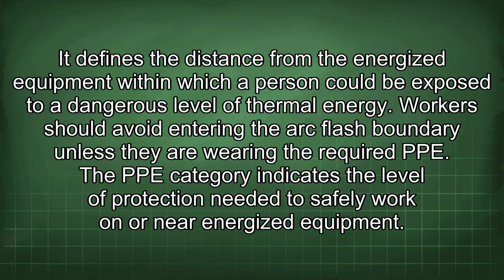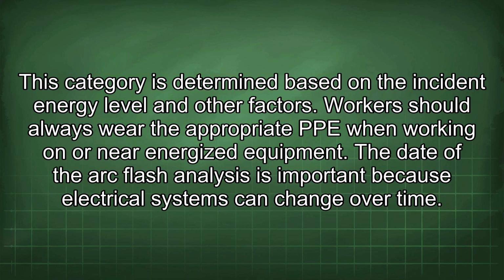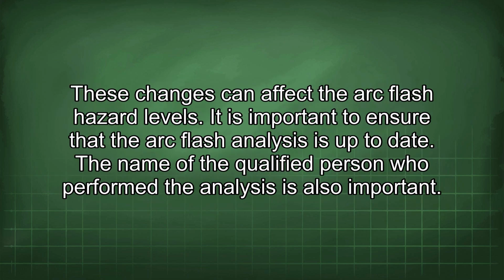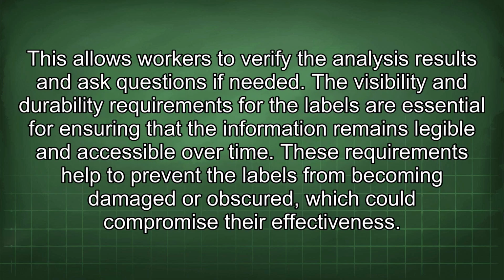The PPE category indicates the level of protection needed to safely work on or near energized equipment. This category is determined based on the incident energy level and other factors. Workers should always wear the appropriate PPE when working on or near energized equipment. The date of the arc flash analysis is important because electrical systems can change over time. These changes can affect the arc flash hazard levels. It is important to ensure that the arc flash analysis is up to date. The name of the qualified person who performed the analysis is also important. This allows workers to verify the analysis results and ask questions if needed.